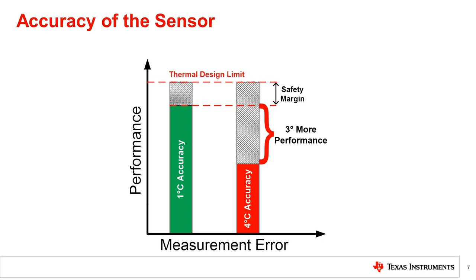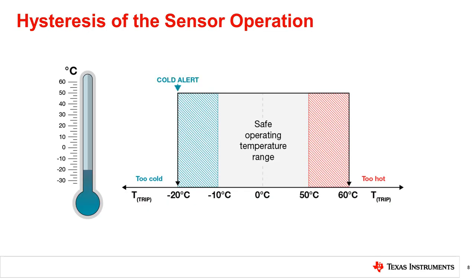In the image shown, you can see a comparison between a 1 degree Celsius accuracy and a 4 degree Celsius accuracy. The 1 degree Celsius accuracy allows you to push the safety margin of your system closer to its thermal design limit. This, in turn, allows for more performance and overall efficiency. Say your system needs to cut off at a temperature of 60 degrees Celsius. Better accuracy may be desirable to ensure that your system powers down.